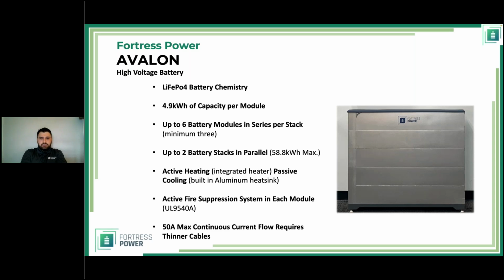You can have a stack with up to 6 battery modules, but the minimum is 3. You start with 3 modules, and based on your energy needs you increase the amount. You can have 2 stacks of batteries working in parallel, which would deliver in total 58.8 kilowatt hours. As mentioned earlier, we have active heating and also passive cooling via an aluminum heat sink, and we have an active fire suppression system in every single module.